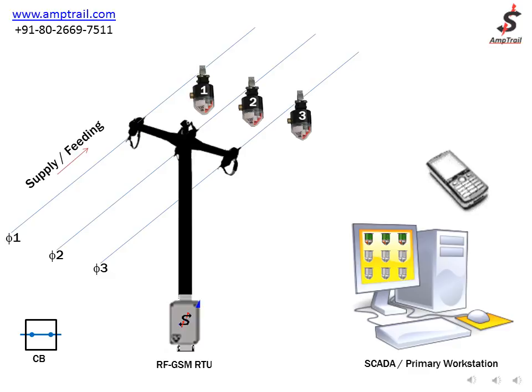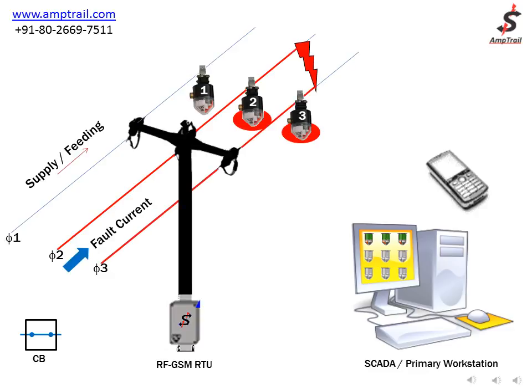Now let us simulate a fault condition — a short circuit condition between phases two and three. As soon as the short circuit occurs, the fault current travels from the source up to the point of short circuit and travels back to the source. FLA3 indicators coming in the path of the fault current trip, thereby indicating a fault. The indicators give a local indication by means of ultra-bright LEDs and a red disc.